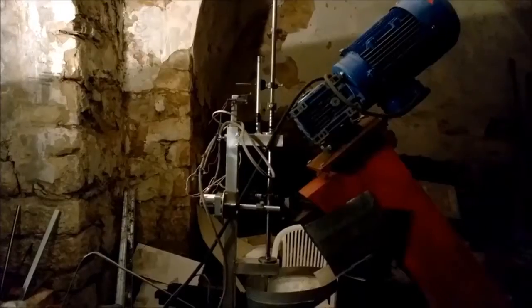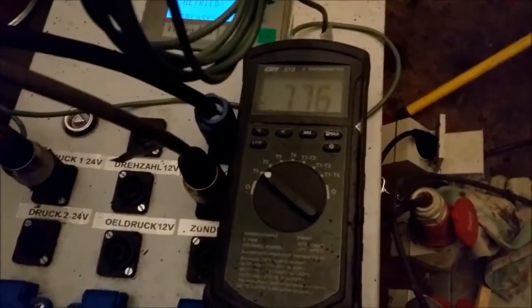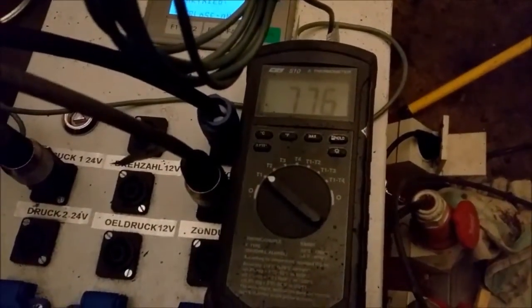We have now two hours, and I think we have reached maximum temperature. I will start up the filter now. We have 760 degrees at the entry of the reduction. I start the filter now — let's see, all okay.